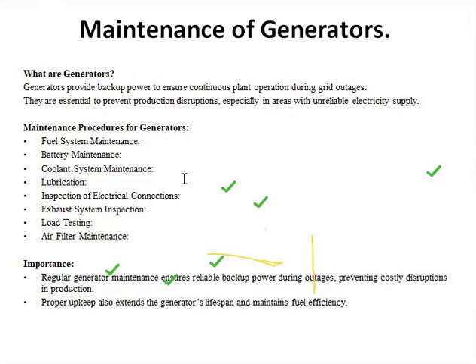So I always check on the coolant system, because generators can overheat without adequate coolant. For instance, if the coolant level is low or there is a leakage in the system, the generator may overheat and shut down. So these coolants are very, very important in the generator. Then we also inspect the electrical connections, maybe some loose connections anywhere in the engine. We tighten them, especially on the relays that take information to the display unit. If they display false information, the generator cannot go on. So always make sure that they are tightened. We also carry out the exhaust system inspection, to make sure that the exhaust is working very well.